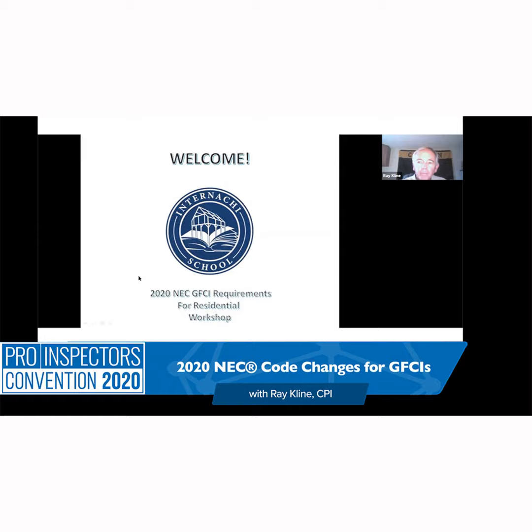What I've got up here is a brief history of the changes that have happened with GFCIs up until about 1999. And like I say, they're still making changes every cycle of the new NEC. You can see back in 1971 that within 15 feet of swimming pools was the first application. And then you just go up through the years. It really didn't start in residential dwellings until about 1973, when it was required for all outdoor receptacles. And where we leave off up here in 1999, there was an exemption issued for dedicated equipment and crawl spaces.